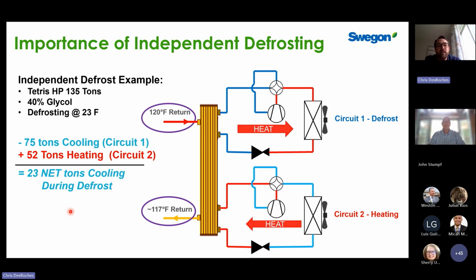So when we look at the individual capacity, this example here is our 135-ton machine. And when we look at the rated capacities of each circuit, what they're doing in the moment that we're defrosting when it's 23F outside, because the circuit that's defrosting is in cooling mode. These are about 65 nominal tons. We get more capacity, 20% more. So this circuit here is actually pulling 75 tons of heat out from the system. And because our heating capacity on the heating side is lower, we're only supplementing 52 tons of heat. So even though we're defrosting independently, we're still producing about 23 net tons of cooling in this moment that we're defrosting for 3-4 minutes.